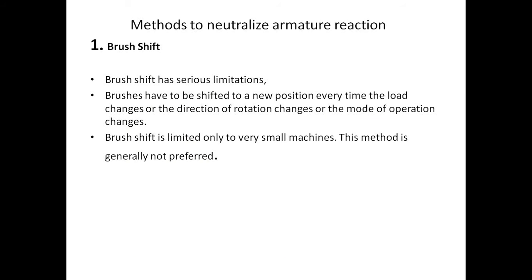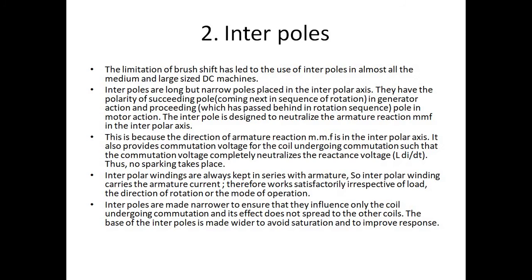Methods to neutralize armature reaction. First one, brush shift. Brush shift has a serious limitation. Brushes have to be shifted to a new position every time the load changes, the direction of rotation changes, or the mode of operation changes. Brush shift is limited to only very small machines. This method is generally not preferred.